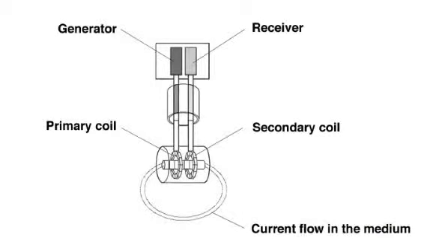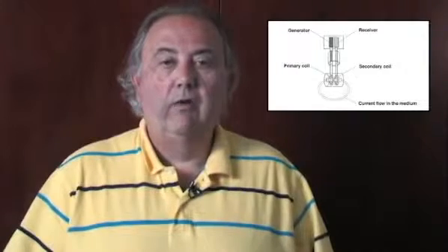Conductivity sensors, the last of the linked three wet chemistry sensors, measure the specific conductivity in micromhos or microsiemens. A mho (M-H-O) is the reciprocal of an ohm (O-H-M). Conductivity is a measure of the specific conductance in a fluid, ranging from zero to very, very high. Distilled water is close to zero, while seawater has a conductivity value of over 30,000 microsiemens. Conductivity sensors are often used to measure salinity, for which they can be calibrated in fluids such as water and other aqueous chemicals. Very often the same transmitter can be used for these measurements because the cells or sensors produce a millivolt output that is very similar, making maintaining these types of analyzers relatively easy. All of these sensors are designed to be easily replaceable — you can even get hot tap versions so they can be changed when the process is running.